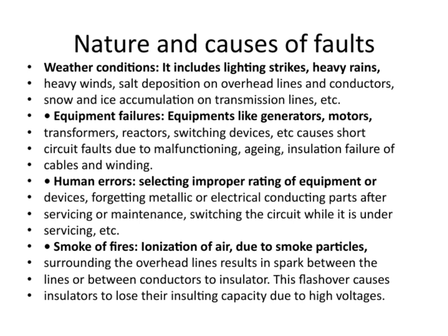Next, equipment failures are another major cause. Components like generators, motors, transformers, reactors, and switching devices can malfunction over time. Issues such as aging, insulation failure of cables, or winding faults often result in short-circuit faults, which can severely impact the system's stability. Human errors, although sometimes less obvious, are equally critical. Mistakes like selecting equipment with improper ratings, forgetting to remove metallic or electrical conducting parts after maintenance, or switching circuits while they are under service can all lead to faults. These errors highlight the importance of careful procedures and vigilance.